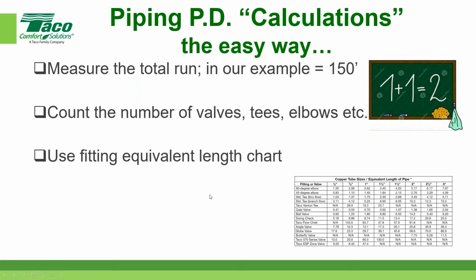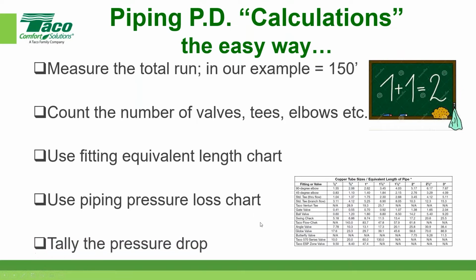Okay, an equivalency chart will tell you an approximation, and I'll explain approximation here in a second, of how much pressure drop that particular fitting or valve or whatever it is would impart on the fluid running through it. Okay, and of course we use these charts, and then we tally it all up at the bottom. We're going to do an example so it'll make sense to you.